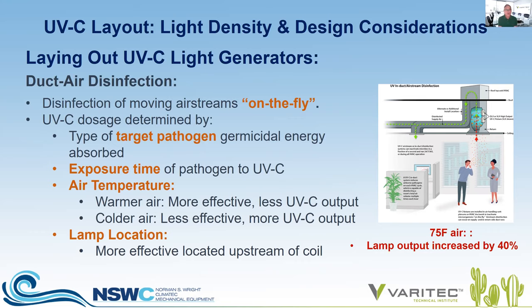Warmer air is more effective and requires less UVC output. Colder air is less effective and requires more UVC output. One recommendation to consider is placing UV in the return air duct to address aerosolized pathogen captured from the space and reduce the risk of it being transmitted into the supply air stream. You have lower velocity air in that configuration, and air at room temperature, so you don't need as much lamp output — consequently reducing the first cost of the application. Then of course we want to look at lamp locations, which will be unique to every building design.